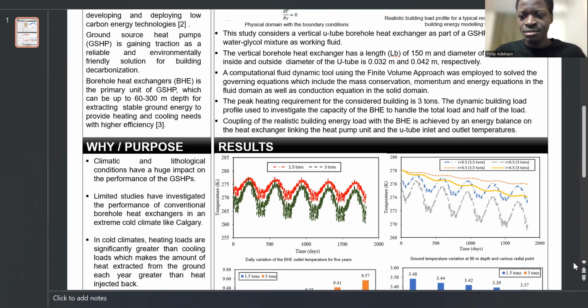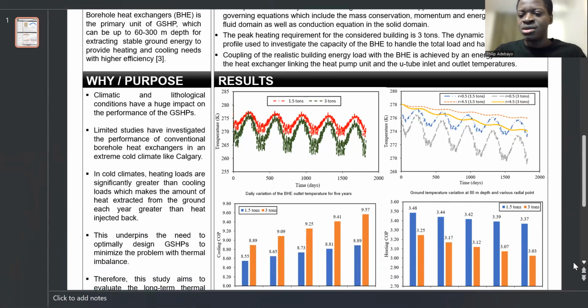Generally, in cold climates, heating loads are relatively higher than cooling loads, and this means that the amount of heat that needs to be extracted from the ground each year is greater than what can be injected back into the ground. So this buttresses the fact that in the design of a ground source heat pump system, especially the ground heat exchanger, we need to optimally design the system to minimize the problem of thermal imbalance. Thermal imbalance occurs as a result of differences in the heat that we are extracting and what we are injecting back into the ground.